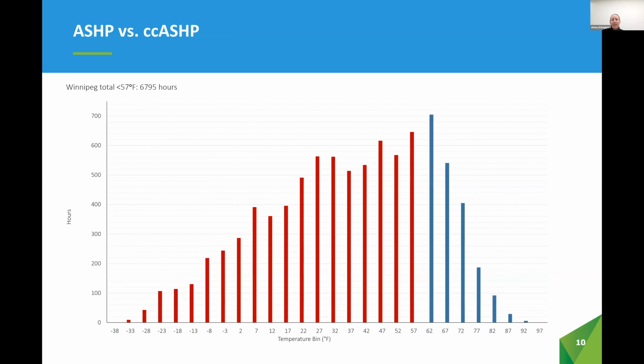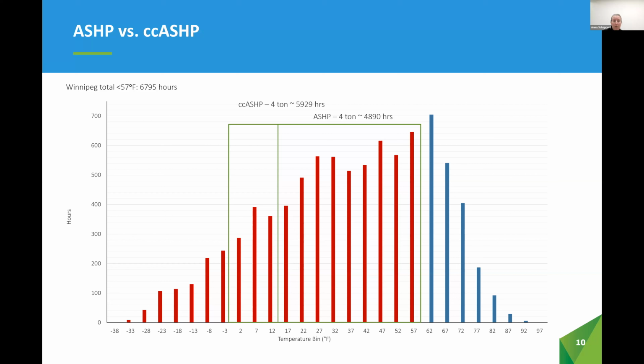While it may be daunting that an air source heat pump's heating output is only capable of meeting a portion of the building's peak heating loss, I also want to illustrate how much of the heating season falls within the unit's capabilities. With that same balance point temperature determined, the air source heat pump can meet the load for almost 5,000 hours of the year. That's 70% of our heating season hours in Winnipeg. The cold climate unit is almost at 6,000 annual heating hours, which is about 87% of our annual heating requirements.